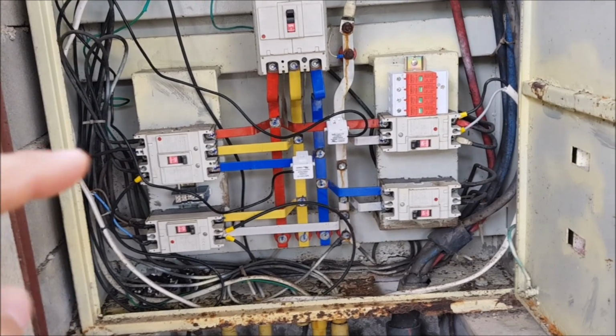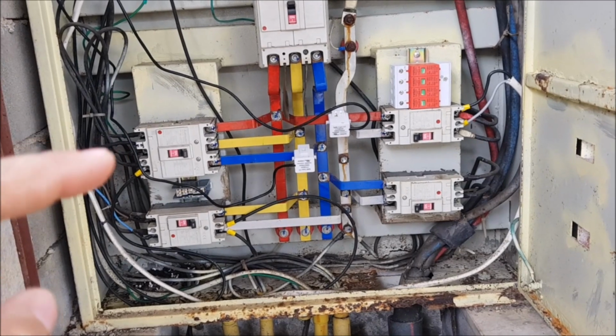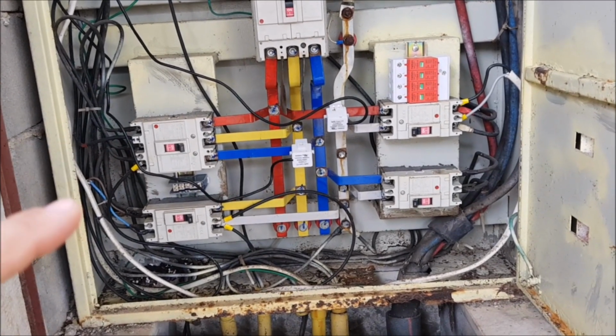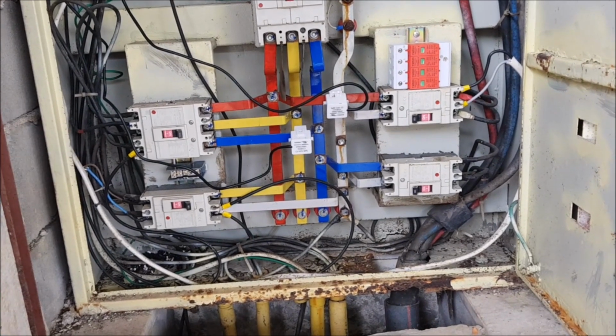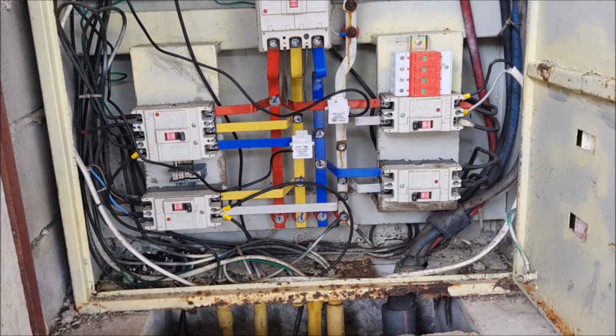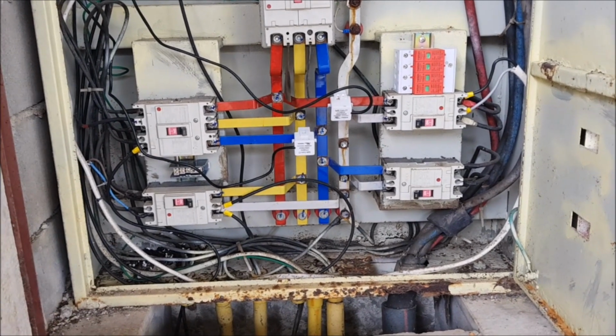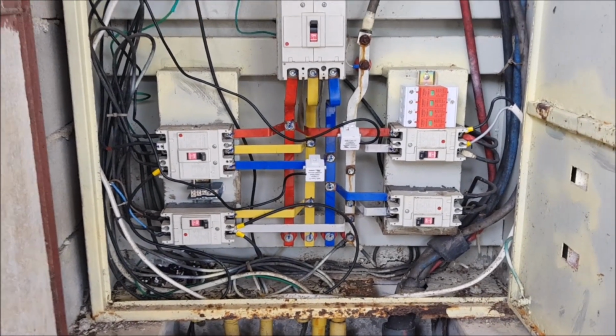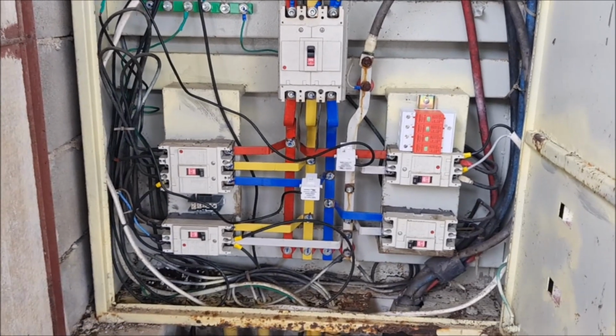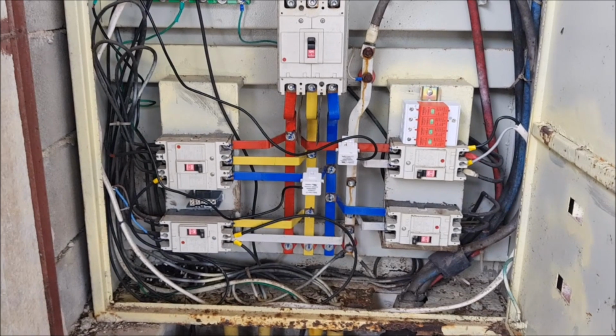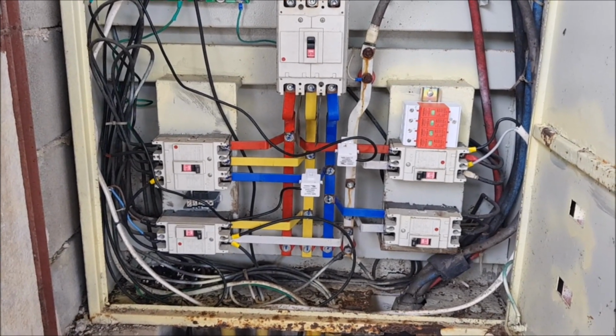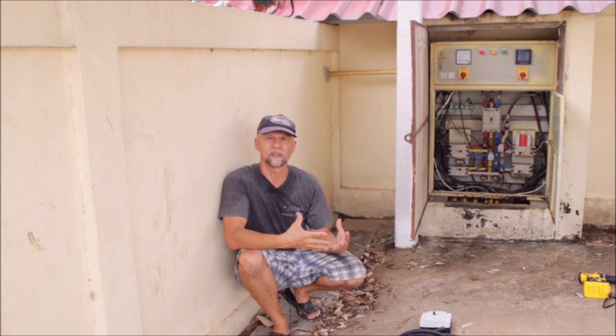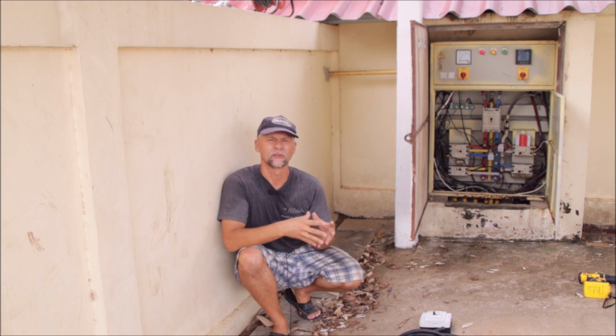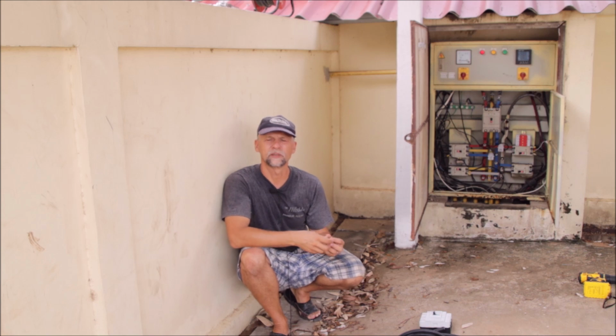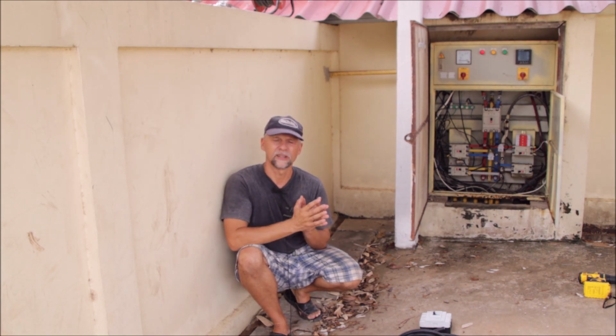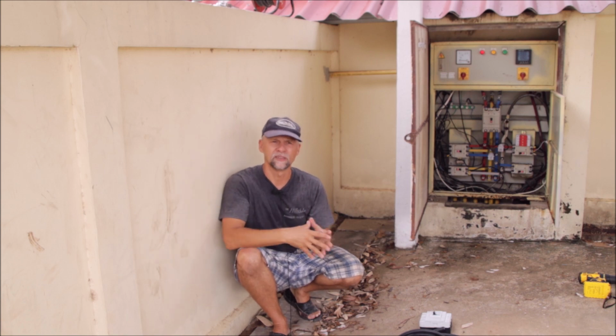When something happens on these wires, which are connected from this side and running to the next distribution point, a short circuit, then this breaker would be responsible to trip. So it's not about overload or even leakage or anything like that, only short circuits. Breakers or fuses in the early parts of the electrical distribution have the purpose of short circuit protection, protecting the cabling from this point to the next distribution point.